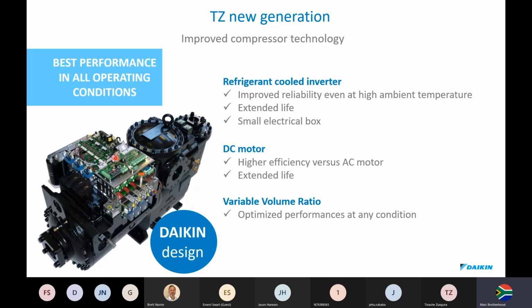The good thing with liquid cooled electronics, even in the event of load shedding, because of pressure differentials within the system, the heat from here will still draw because of the pressure difference, and the cooling cycle is still going to take place as it draws subcooled liquid out of the condenser. So it's going to continually cool without any active power.